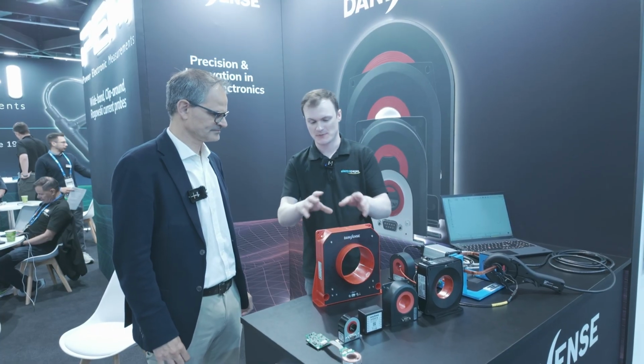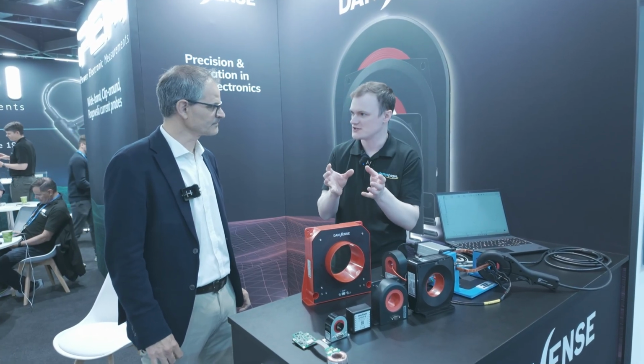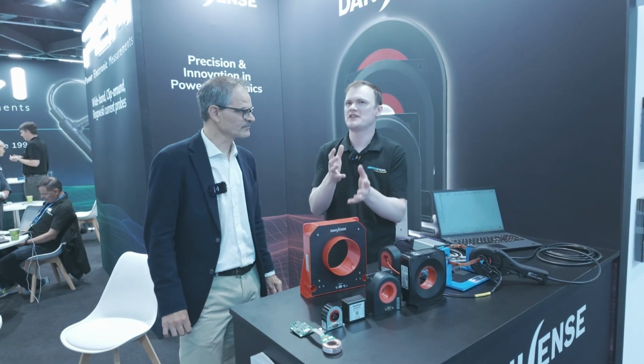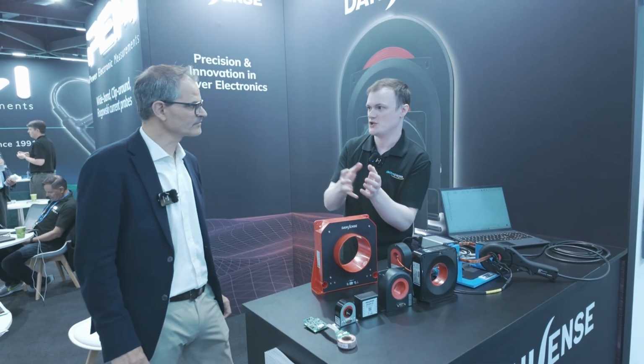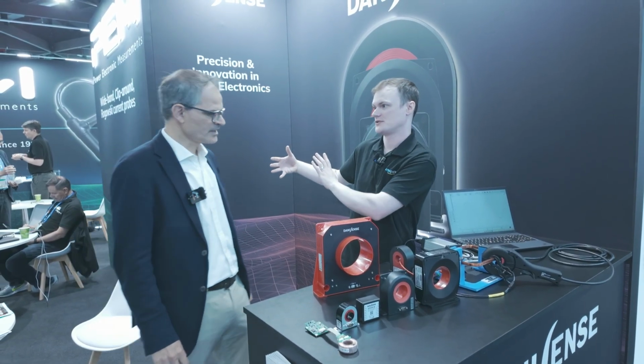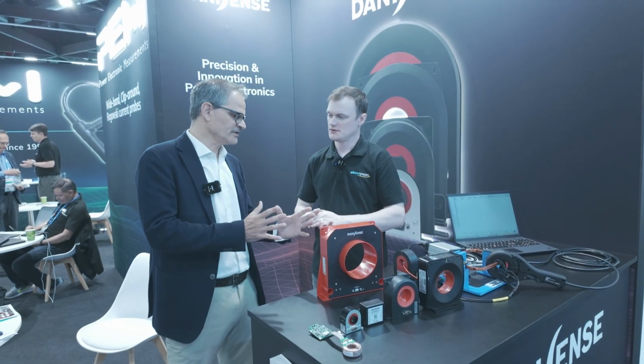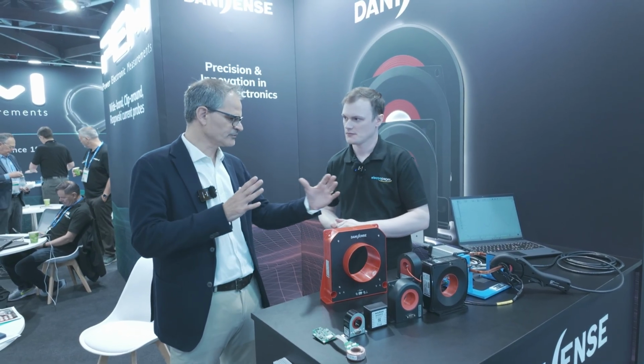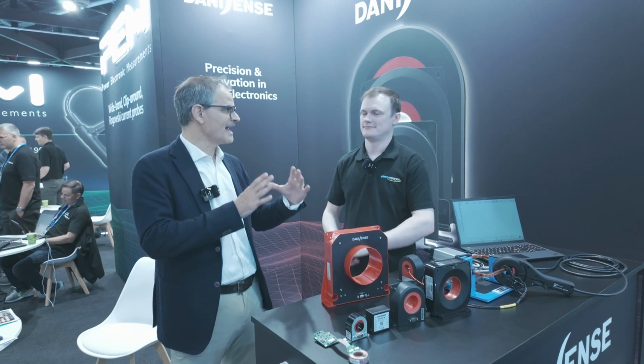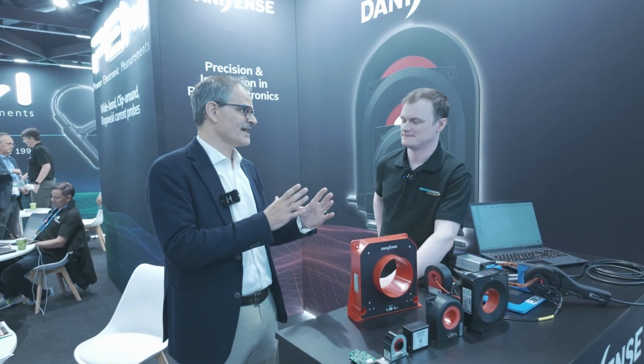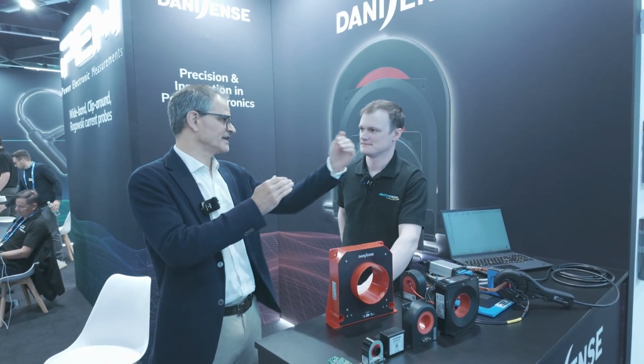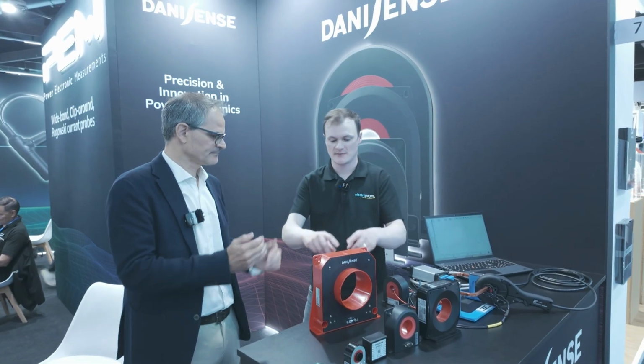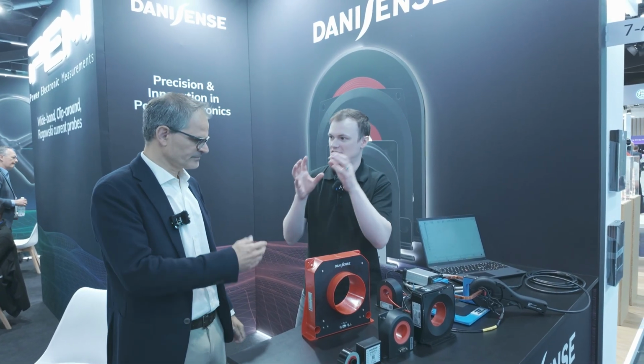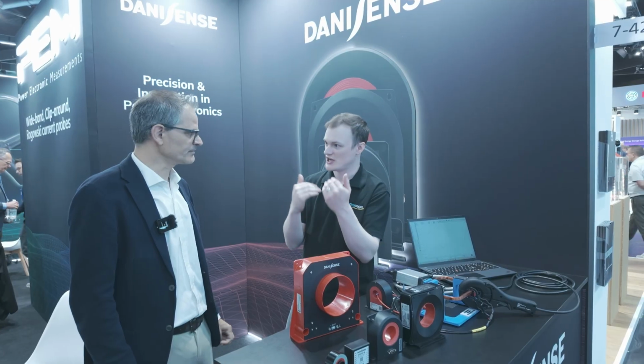Is that to do with the magnetics being saturated at those currents? Is it anything to do with that, or what makes it hard to measure an amp when you're dealing with 4,000 amps? The real challenge is the linearity, which needs to be really high, and the offset, and on top of that, the offset drift as well.